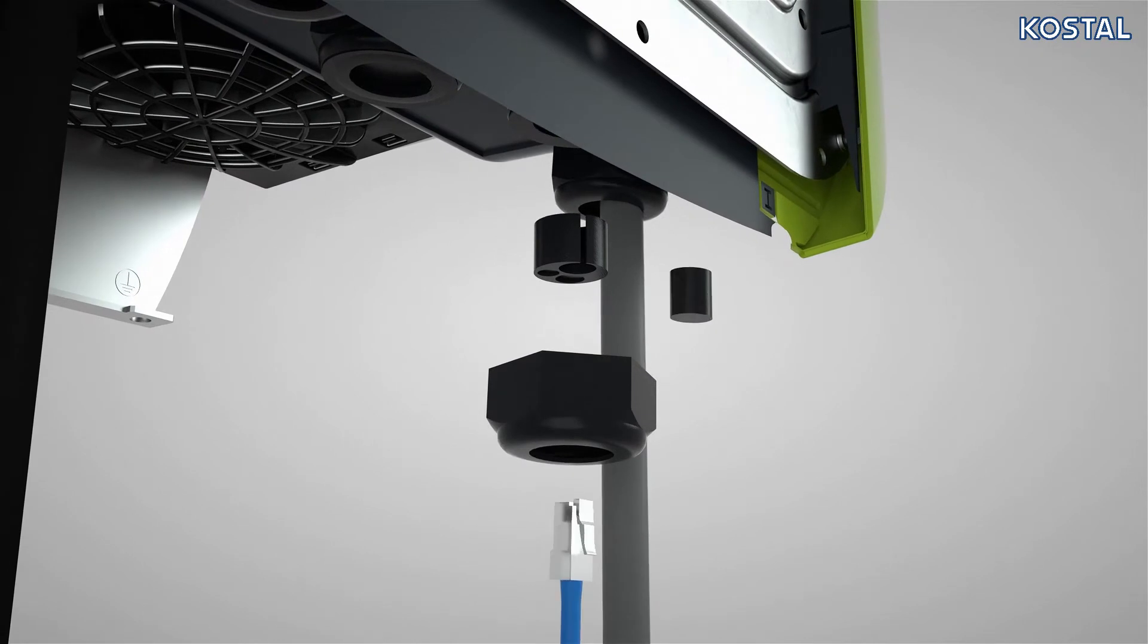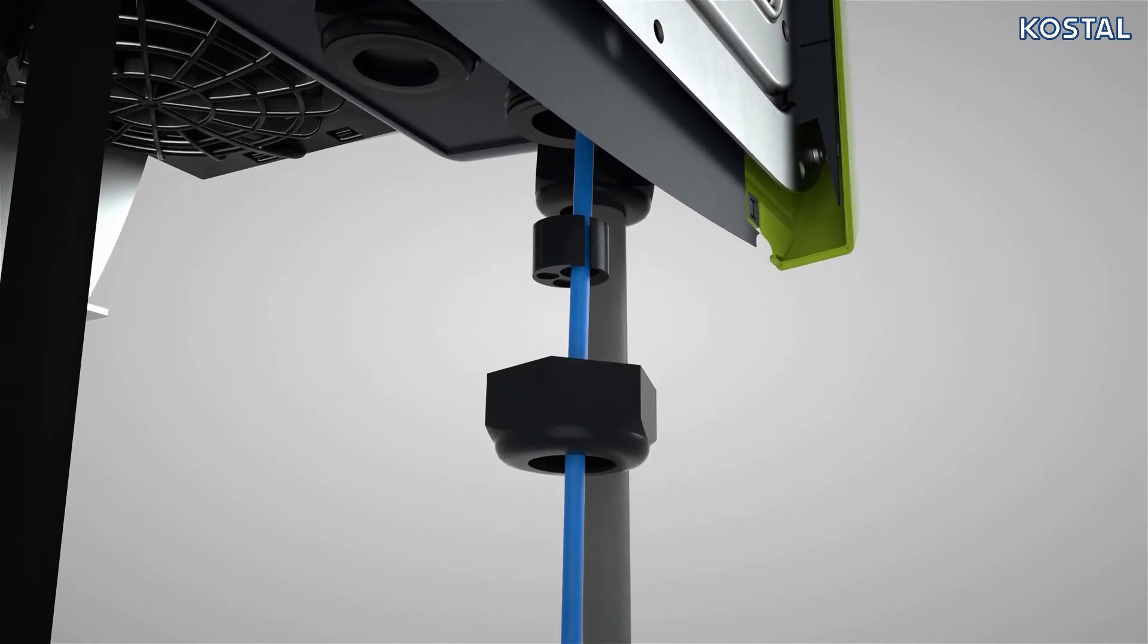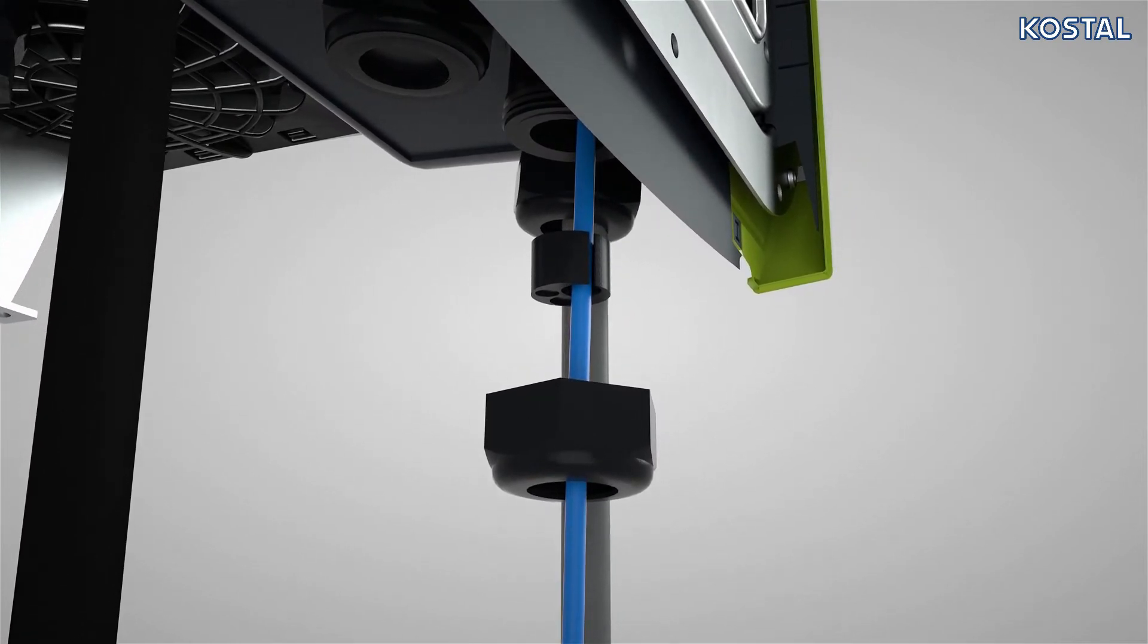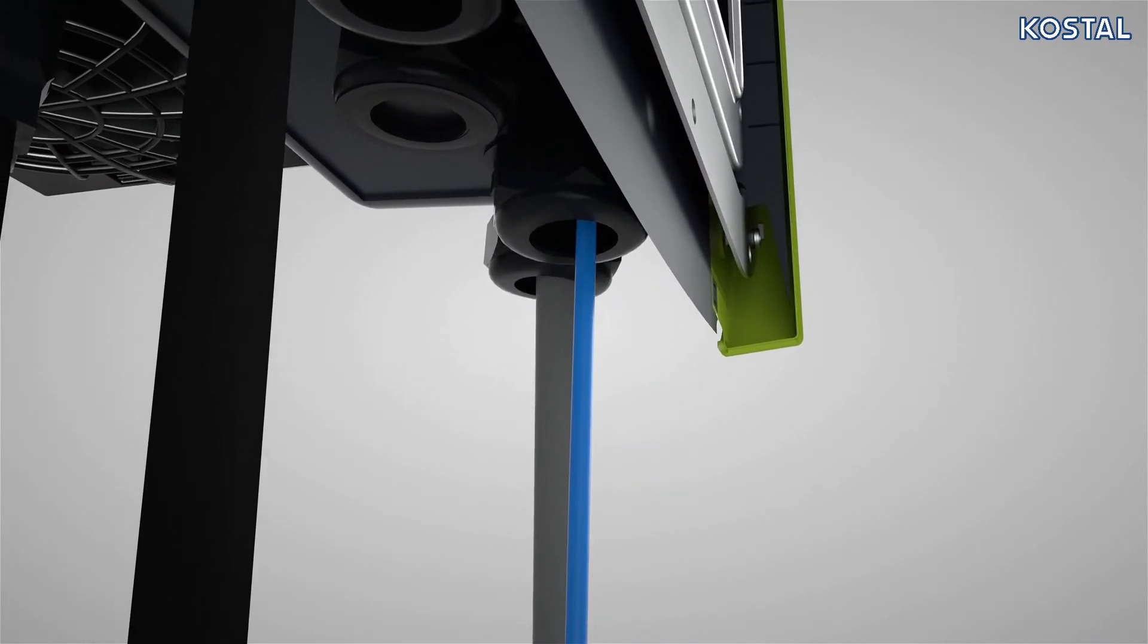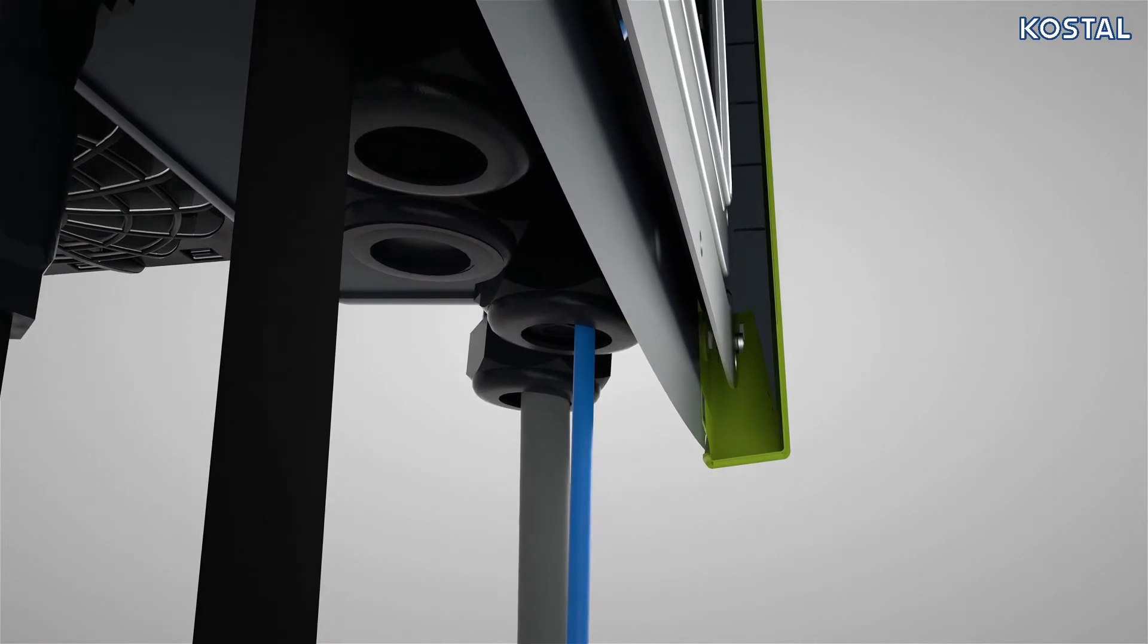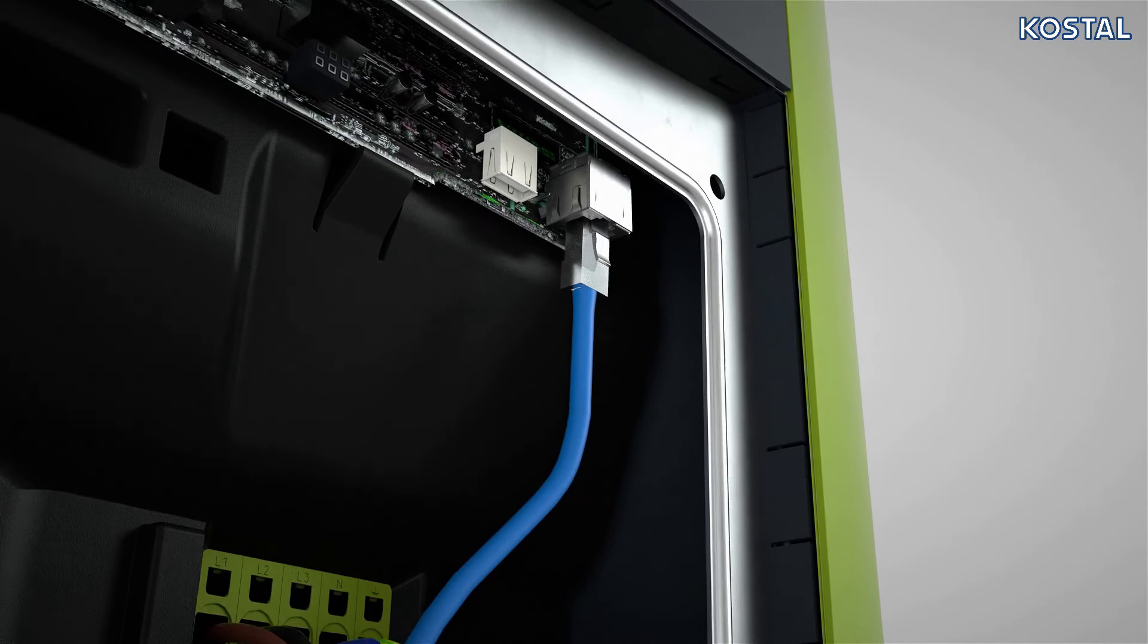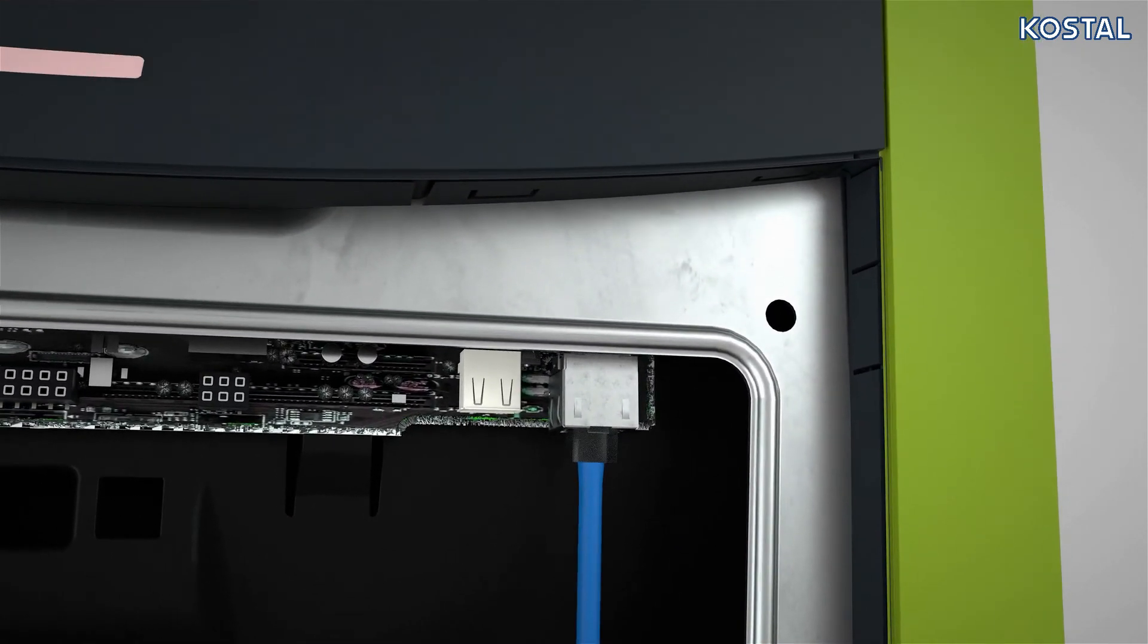Guide the LAN cable through the cable gland and then through the cable aperture on the inverter. If necessary, replace the plug seal in the cable gland with the appropriate plug seal from the scope of supply. Note the specified torque for the cable gland. Connect the network cable with the RJ45 socket on the smart communication board.